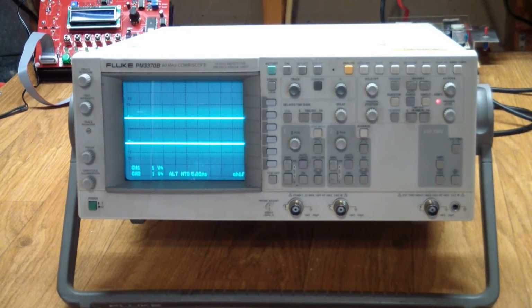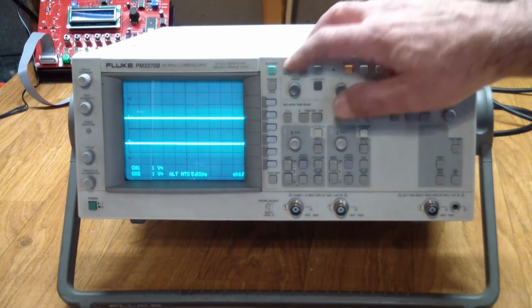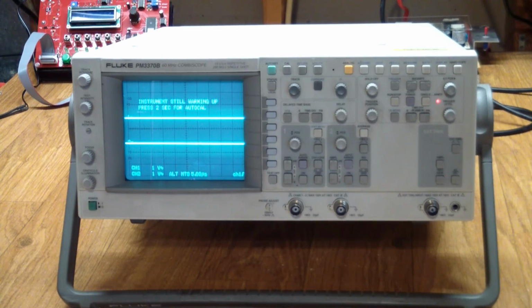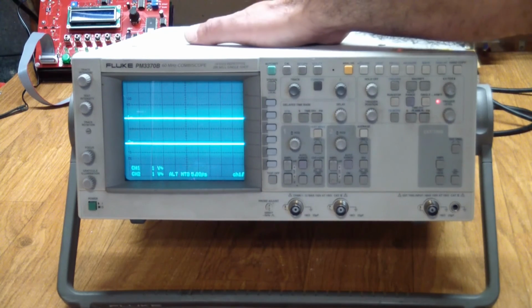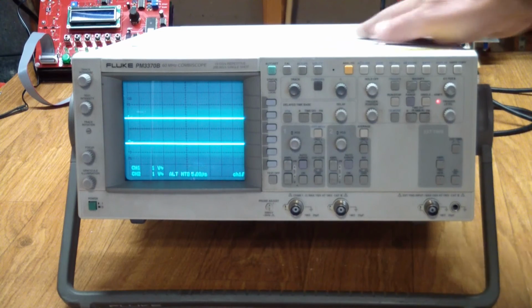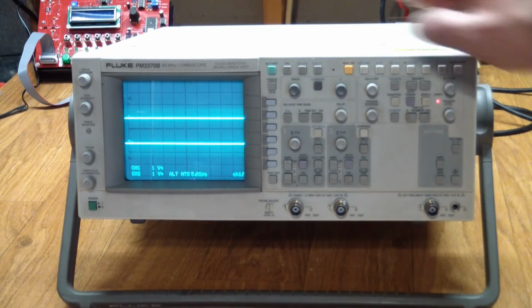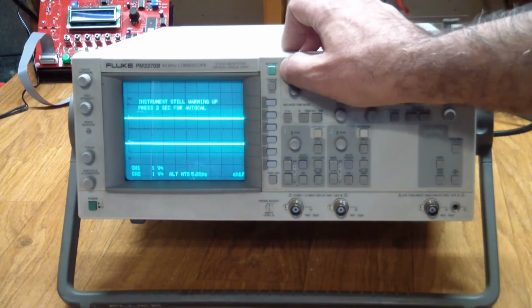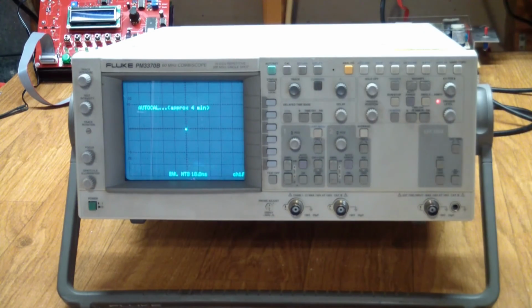And what I'm going to do is have the instrument calibrate itself. That's usually a pretty deep test to see if a lot of the subsystems are working. Now I pressed the cal button, and it keeps saying instrument still warming up, but feels like it is warmed up. So let's see what gives. So that's going to take a little bit, and some final words on this.